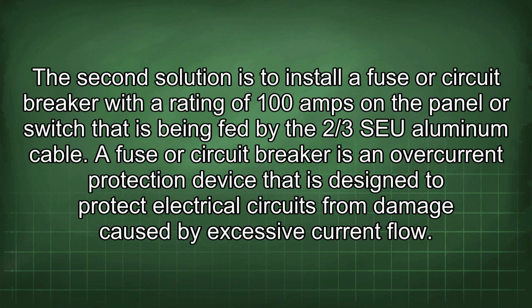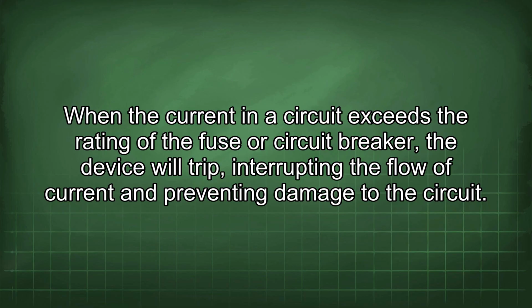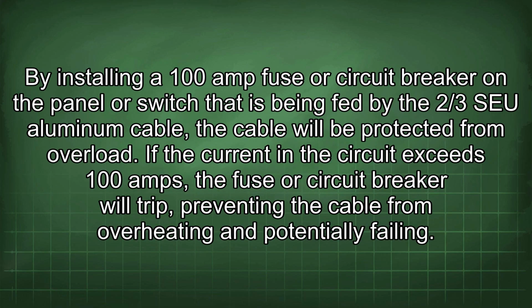The second solution is to install a fuse or circuit breaker with the rating of 100 amps on the panel or switch that is being fed by the 2/3 SEU aluminum cable. A fuse or circuit breaker is an overcurrent protection device that is designed to protect electrical circuits from damage caused by excessive current flow. When the current in a circuit exceeds the rating of the fuse or circuit breaker, the device will trip, interrupting the flow of current and preventing damage to the circuit. By installing a 100 amp fuse or circuit breaker on the panel or switch that is being fed by the 2/3 SEU aluminum cable, the cable will be protected from overload. If the current in the circuit exceeds 100 amps, the fuse or circuit breaker will trip, preventing the cable from overheating and potentially failing.